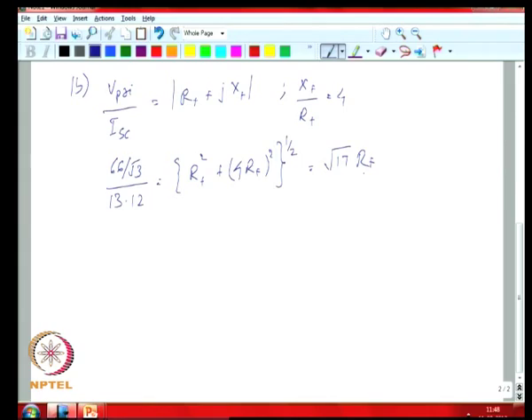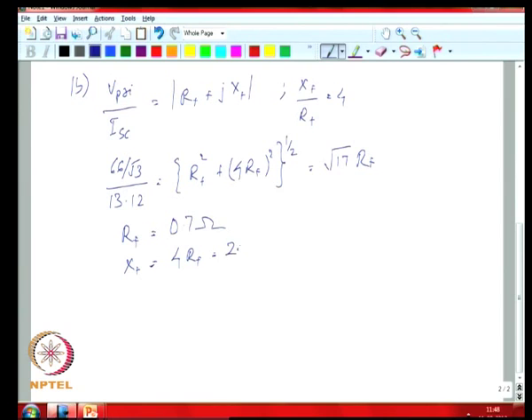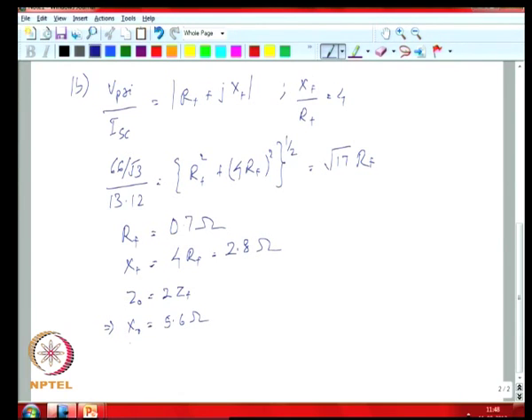You have this particular example because your x-by-r ratio is 4. You can then calculate: r-plus is 0.7 ohms, x-plus is 4 times r-plus equal to 2.8 ohms. Your z-naught is 2 times z-plus, which means x-naught is 5.6 ohms and r-naught is equal to 1.4 ohms.